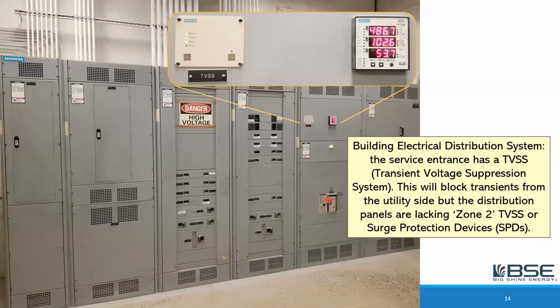Now, here's one example. This is just a facility that we serviced. And as you can see, it has modern electrical distribution equipment. Siemens is a very good manufacturer. They make excellent equipment. And this building has what's called a TVSS, a transient voltage suppression system. This is what we would call zone 1 surge protection because it would block very high surges of electricity, of voltage that would be coming from outside the building.